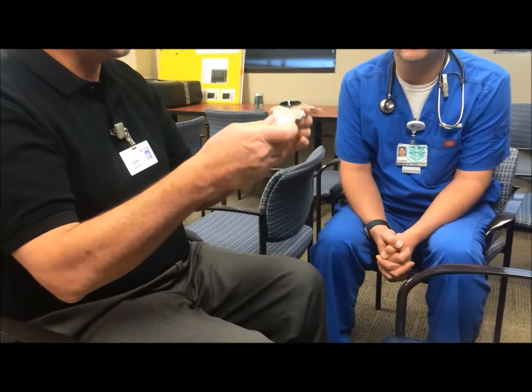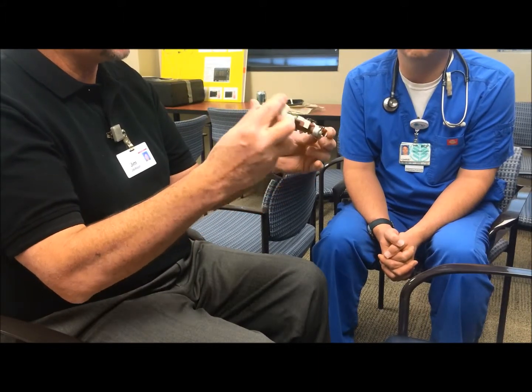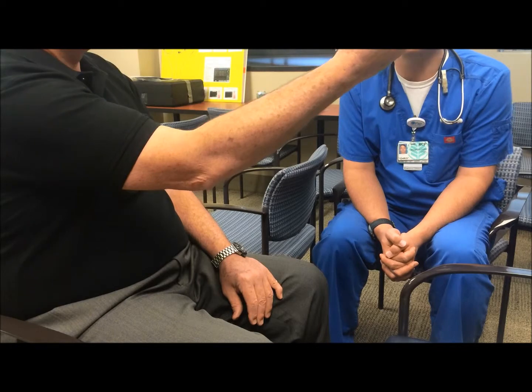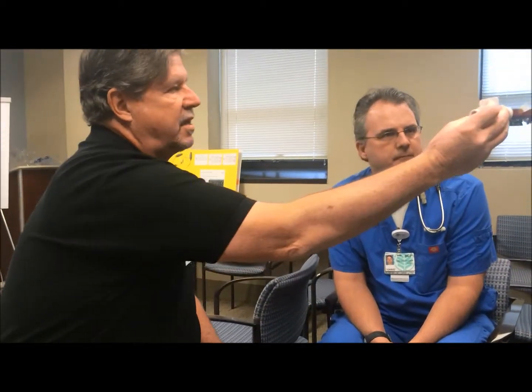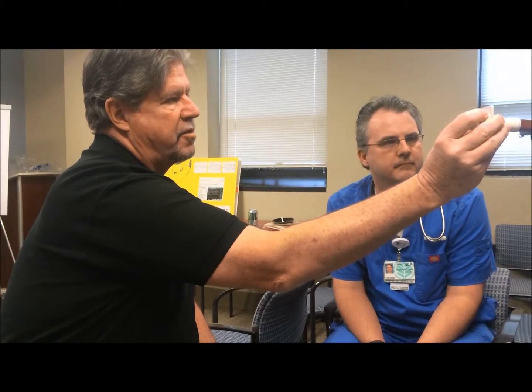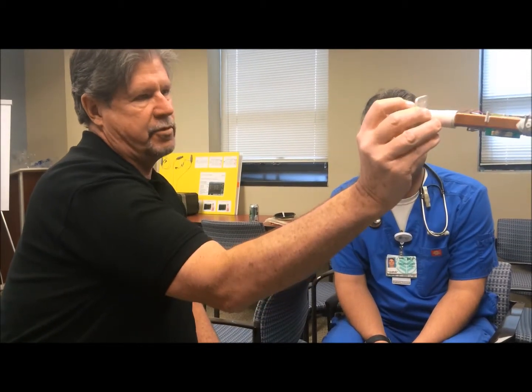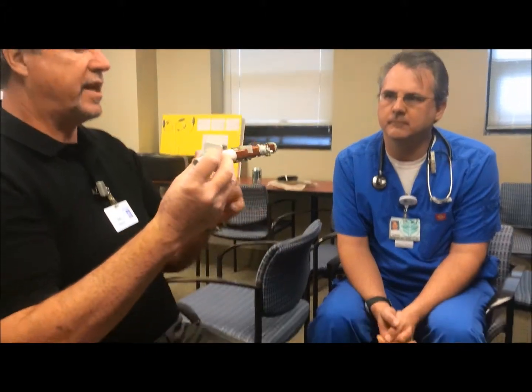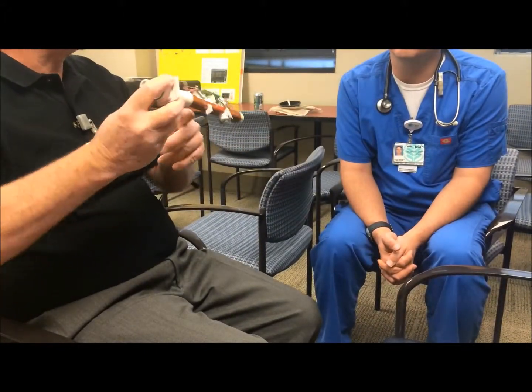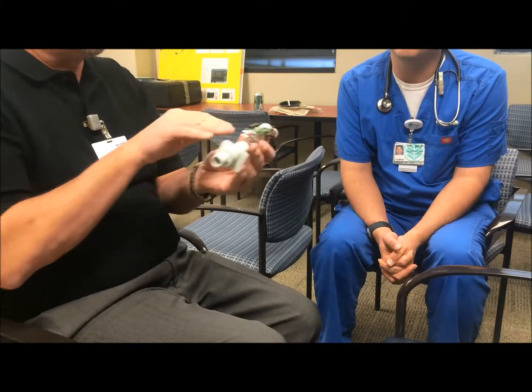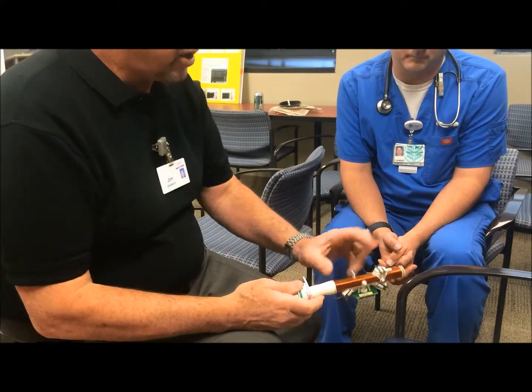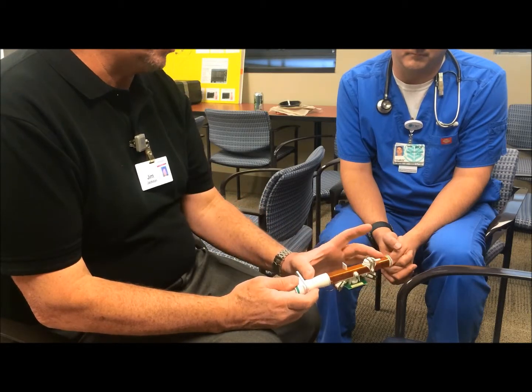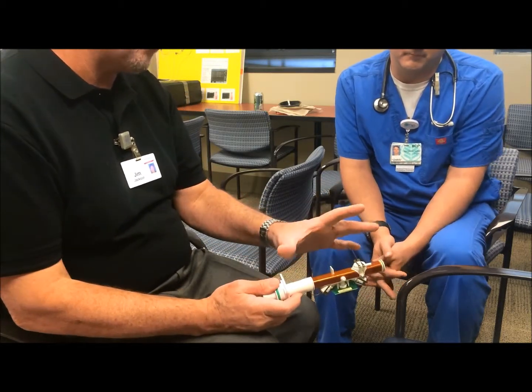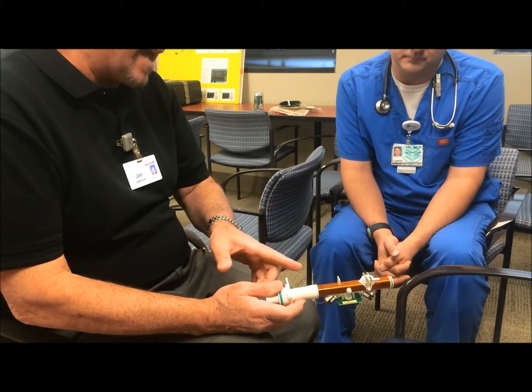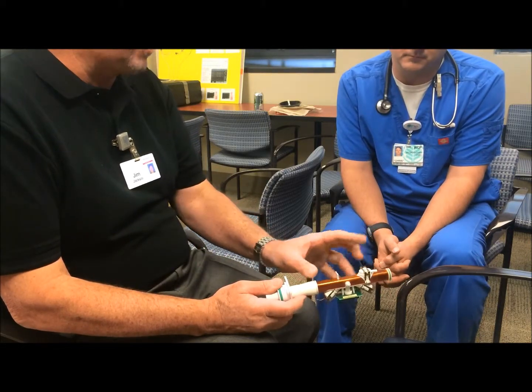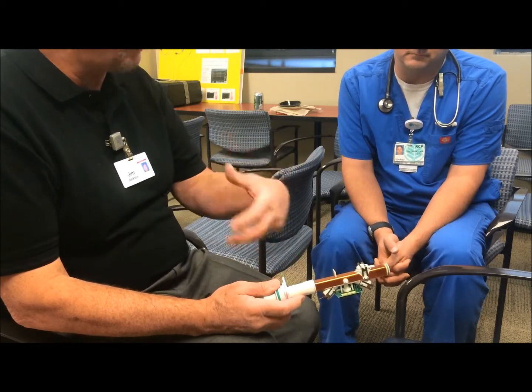This is all there is to the internal workings of the cassette. It's all one piece. When you look through the cassette, there's nothing in that channel other than that little thing you see sticking down from the top, or on the side. That's a temperature transducer, or temperature probe. It measures the temperature inside. This foil is a heater foil that heats the internal channel up to about 102 degrees, so that as the patient's exhaled gas goes through here, it limits the amount of condensation that occurs by keeping that water in suspension.